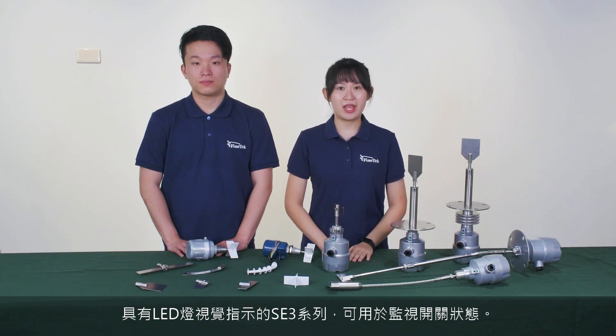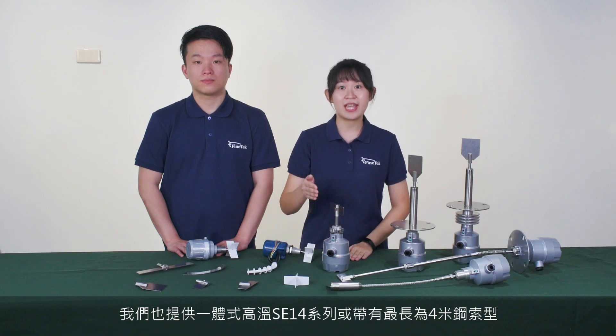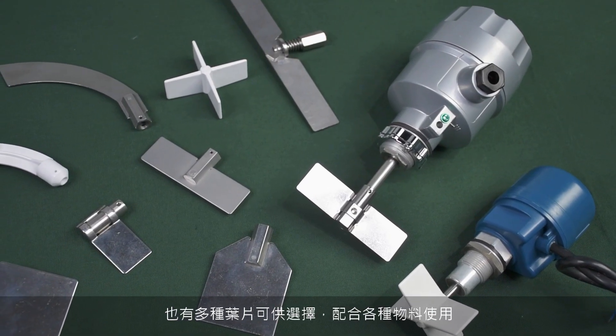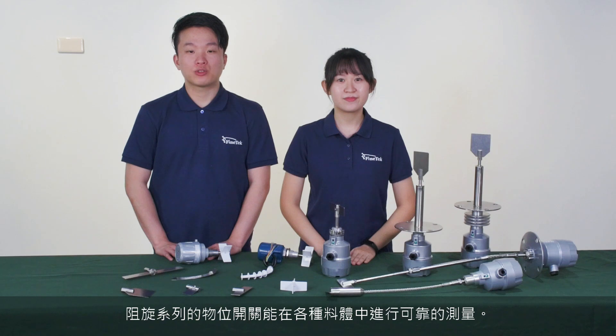The SE3 series with LED indication can be used to monitor switch status. Its torque is small and can be used in small tanks to detect lower gravity material. We also provide compact model SE14 series for high temperature, and cable series that can be up to 4 meters. The SE17 series, the explosion-proof model, is used in hazardous areas. The operation temperature is from minus 20 degrees to 190 degrees. We also provide a variety of paddles to choose and to match materials of all kinds. Regardless of the tank types, the rotary paddle level switch can perform reliable measurement in various materials.